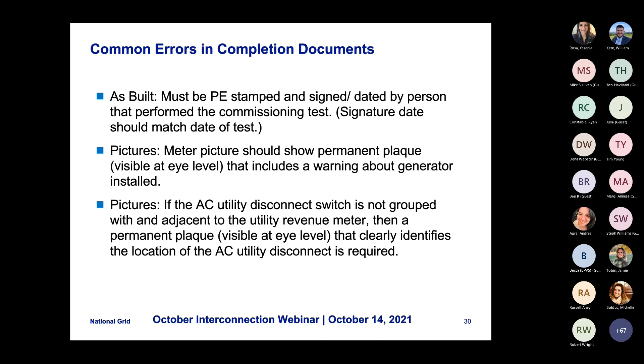For projects greater than 60 kW in Massachusetts, we do require evidence of insurance. So you can refer to the ISA as well as the tariff for some of the specifics to your project and the size of your project for the insurance requirements, but all projects will require that form to get the interconnection ATI. For qualifying facilities, the documents that we do require are the Schedule A. Greater than 60 kW, we'll want the W9, the ACH, the supplier enrollment form, and then we will continue with the asset registration as well for projects greater than 60 kW, and then ATI will be delivered.